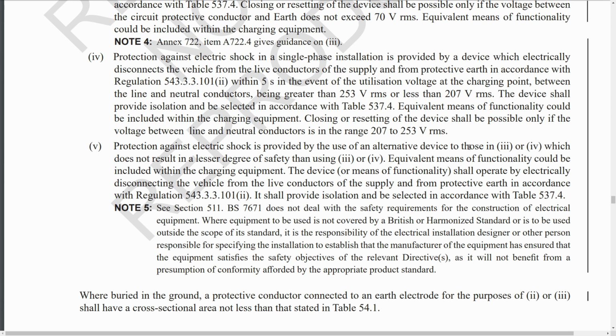And it does this disconnection when the voltage between the line and neutral conductors is greater than 253 volts or less than 207 volts. Now, those particular voltages are the standard range for voltages in the UK. That's your 230 volts plus or minus the percentages. And the device shall provide isolation of these selected in accordance with that table. Equivalent means of functionality could be included in the charging equipment, and in fact probably will be. Closing or resetting shall be possible only if the voltage between line and neutral is in the range of 207 to 253.